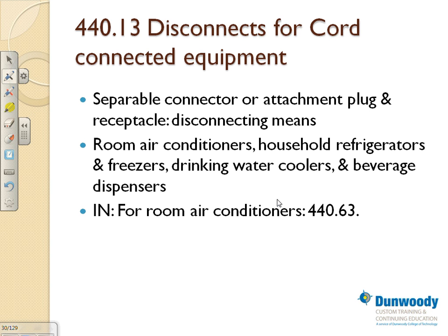Disconnect for, we're still in the HVAC equipment. For cord-connected equipment, you can use a connector or attachment plug and a receptacle as a disconnect means. Most of the time that's for smaller equipment, good examples being window air conditioning, refrigerating equipment, freezers, drinking fountains, and all this good stuff. There's some info you need to pay attention to for window air conditioning. But plug-in is not your chiller. You're not going to plug in your chiller, right? Your chiller is going to have a horsepower and amp rated disconnect right next to it, on it, or near it. That's for smaller equipment.